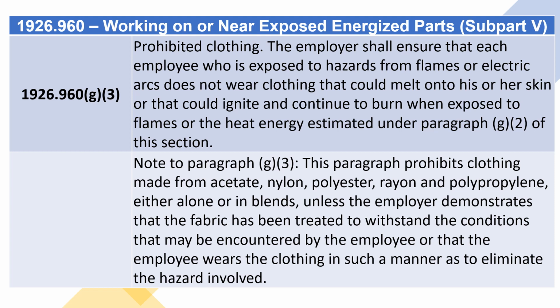1926.960(g)(3) Prohibited clothing. The employer shall ensure that each employee who is exposed to hazards from flames or electric arcs does not wear clothing that could melt onto his or her skin or that could ignite and continue to burn when exposed to flames or the heat energy estimated under paragraph (g)(2) of this section. Note to paragraph (g)(3): This paragraph prohibits clothing made from acetate, nylon, polyester, rayon, and polypropylene, either alone or in blends, unless the employer demonstrates that the fabric has been treated to withstand the conditions that may be encountered by the employee, or that the employee wears the clothing in such a manner as to eliminate the hazard involved.